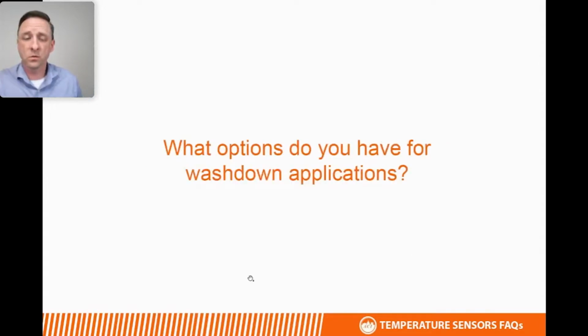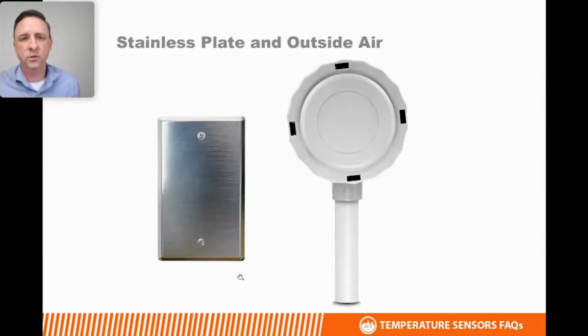For indoor wall mount sensors, what options do we have for splashdown or washdown applications? For these applications, we typically recommend using an outdoor air sensor indoors, and that's the sensor that you would see on the right-hand side of your screen. That's available in a number of different enclosures, including NEMA 3R and NEMA 4X housings, and can withstand direct spray and washdown and splashdown applications.